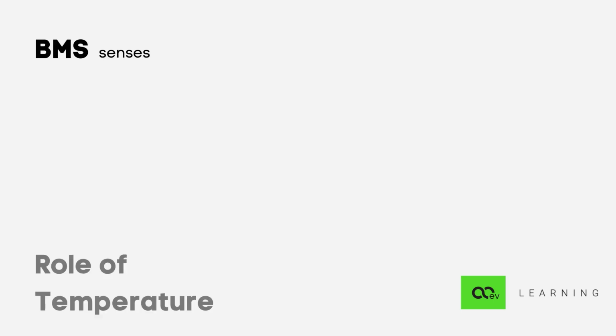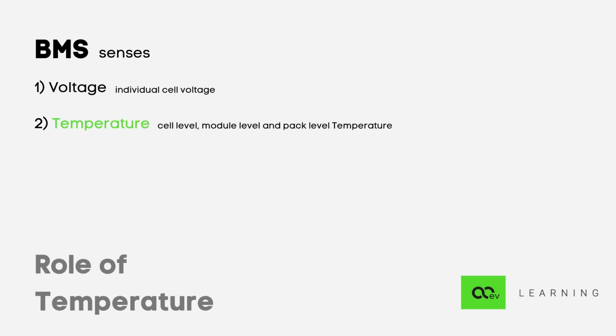Now what does the BMS sense? First is voltage, including individual cell voltage, which is a critical input to the SOC and SOH estimation algorithms. It's essential for protection and is measured using ICs. Second is temperature, sensed at the cell level, pack level and module level, mostly measured using thermistors, and is a critical input for the thermal management system.